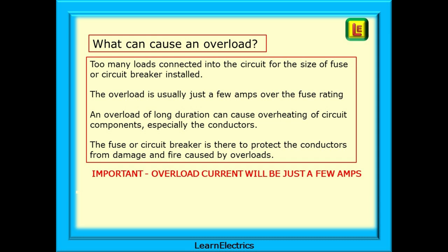But an overload of long duration can cause overheating of circuit components, especially the conductors. After several minutes, this will cause the breaker to trip in order to protect the circuit. The fuse or circuit breaker is there to protect the conductors from damage and fire caused by overloads. Remember, an overload is often just a few amps greater than the fuse rating and may take several minutes to cause the breaker or fuse to operate.